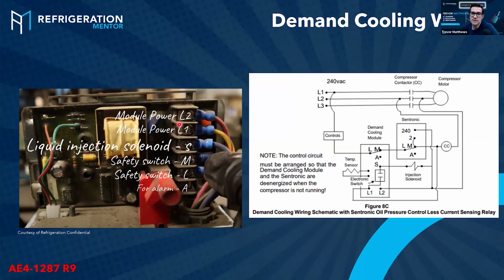So here's the module power. So this is the powered up. So you need power to that. This is the solenoid. So if you look right over here on the wiring diagram, there's a solenoid, there's your M, there's your L, M, A, L1, L2. So L1, L2 down here, my sensor is right here. Then I got M, L, and A. Okay, just remember, always follow the manual when you're wiring it up. That's what I meant to say.